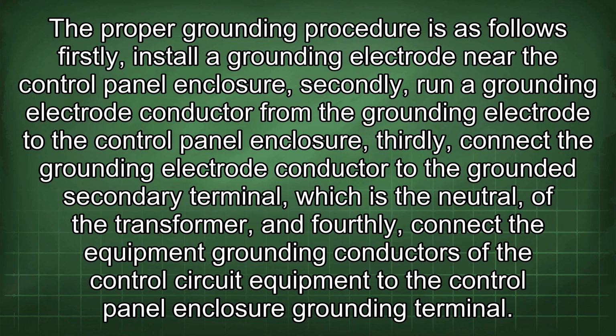The proper grounding procedure is as follows: firstly, install a grounding electrode near the control panel enclosure. Secondly, run a grounding electrode conductor from the grounding electrode to the control panel enclosure. Thirdly, connect the grounding electrode conductor to the grounded secondary terminal, which is the neutral of the transformer. And fourthly, connect the equipment grounding conductors of the control circuit equipment to the control panel enclosure grounding terminal.